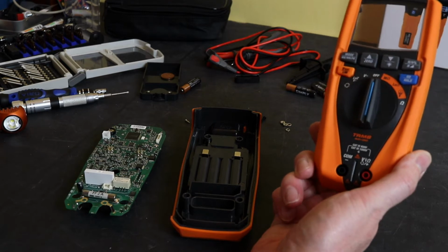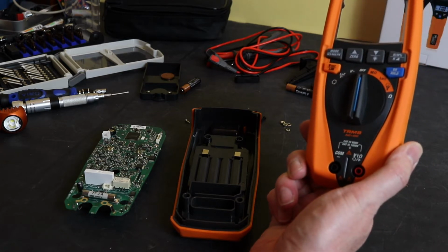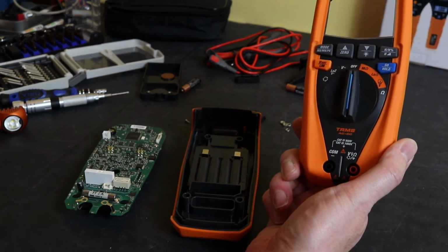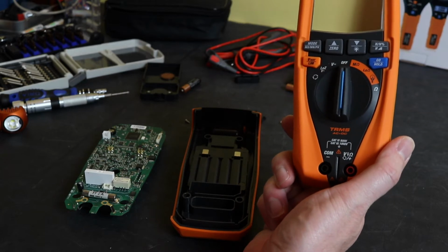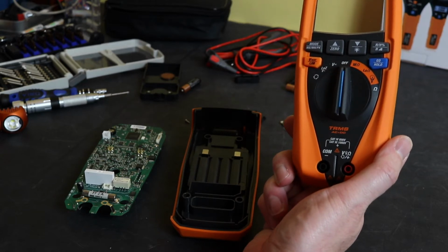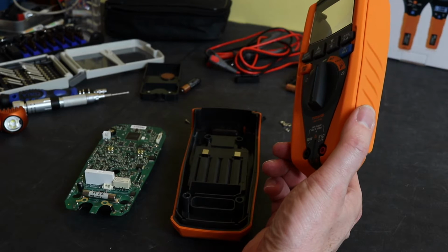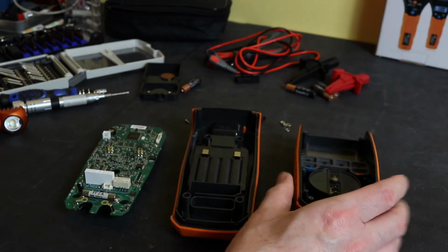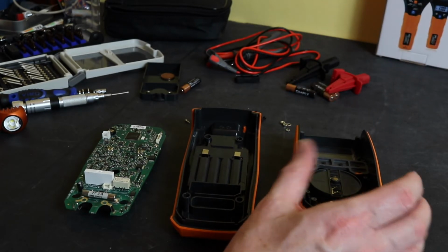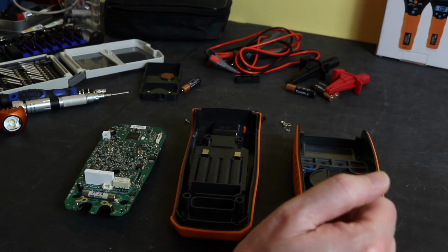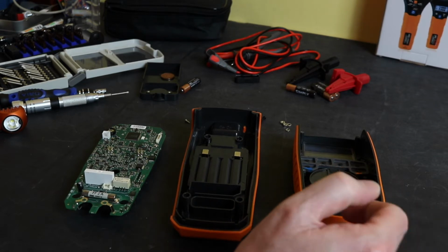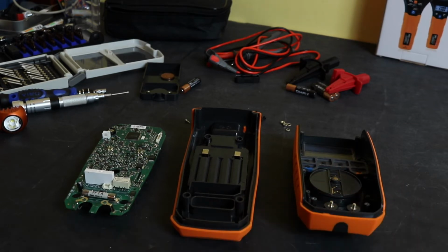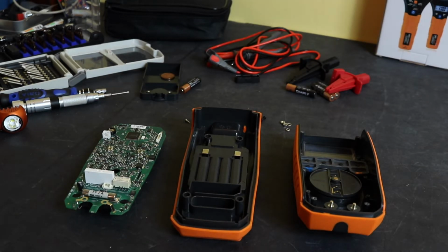This instrument is actually claiming Cat 4 600 volts, Cat 3 1000 volts. You can see underneath the rotary switch there and above the jacks. So I'll take a look at that, and also when it's an unusual instrument that I've not seen before, I like to try and find out if it's an original build by that manufacturer or if it is actually a clone. And if it is a clone, sometimes the original manufacturer leaves a few little clues inside.